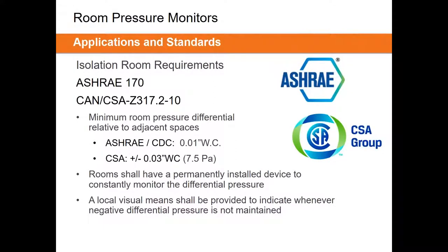ASHRAE 170 gives us very clear-cut requirements for isolation rooms. First, it gives us minimum room pressure differentials — we need 0.01 inches of water column in each of these spaces. It specifies whether positive or negative depending on room type. Very clearly, the standard states rooms shall have a permanently installed device to constantly monitor the differential pressure. Isolation rooms require room pressure monitors — you can't have one without the other.